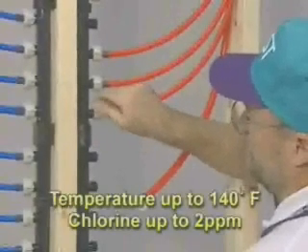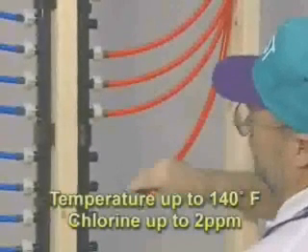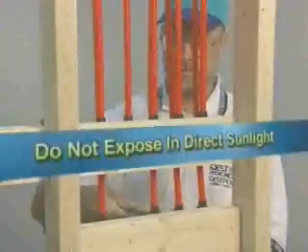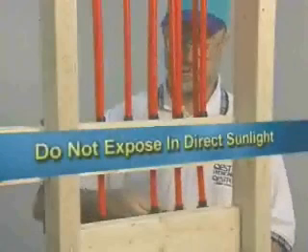Zurn PEX tubing may be installed in circulating hot water plumbing loops, like those found in hotels and motels, when the temperature is 140 degrees Fahrenheit or less and the chlorine in the water is two parts per million or less. Zurn PEX tubing should never be used in areas exposed to direct sunlight, because like most plastics, Zurn PEX can be attacked by the ultraviolet component of sunlight.